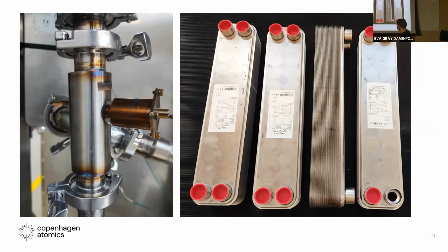We're also using Alfa Laval's Alfa Nova plate heat exchangers. To our knowledge, Alfa Laval is the only one that makes plate heat exchangers where the brazing compound is stainless steel rather than a stainless steel alloy or copper braze, which is great because you could potentially use it in a reactor. These are rated for about 30 bar, and we have around a quarter bar pressure drop across the heat exchanger. Even though they haven't been rated for nuclear use, this is one of the things we want to get approved for molten salt applications.